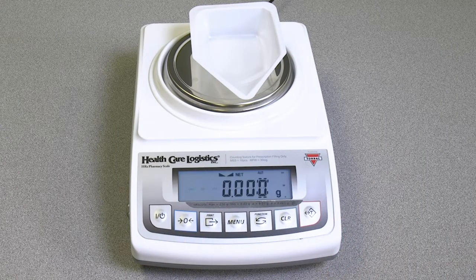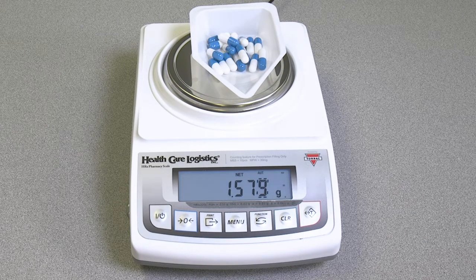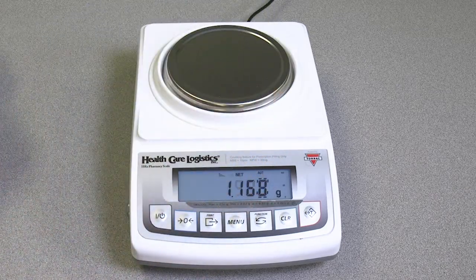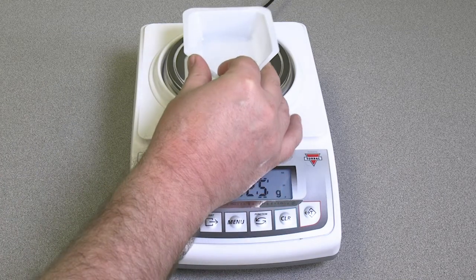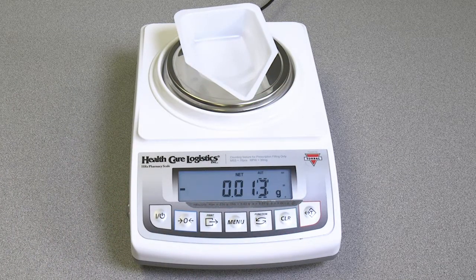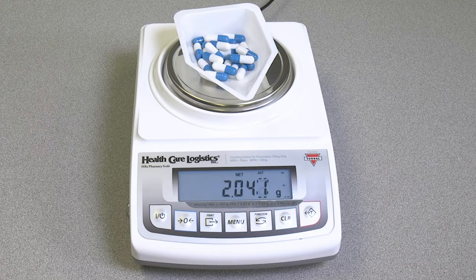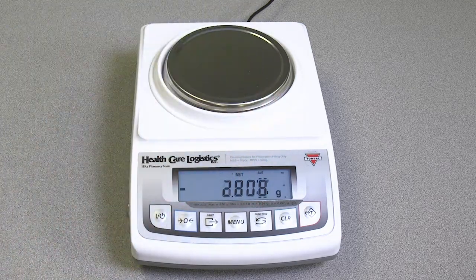Now that the scale is in weighing mode and has been tared, simply fill the canoe with your product, place it on the scale, and wait for the stabilization notification to appear. Then you can be assured that the correct weight is on the display. Should you decide to use a different but similar container, then place an empty container on the scale and make sure the weight is 0. If not, then you must re-tare the scale. Also, if you should use an entirely different container, then again, you will need to re-tare the scale.